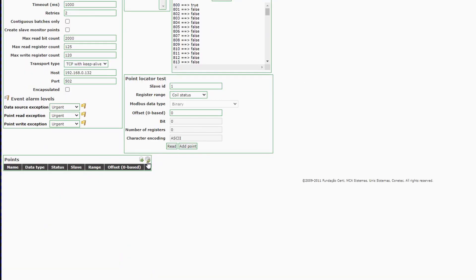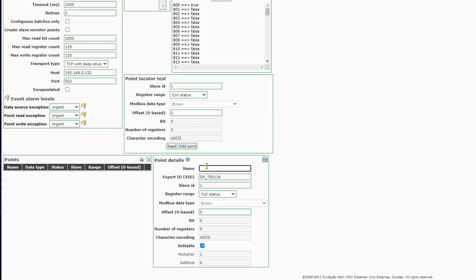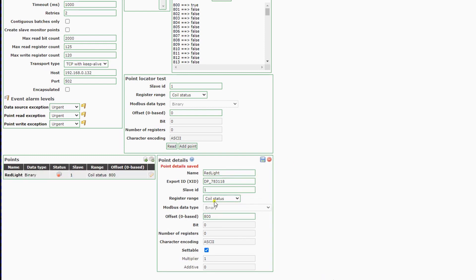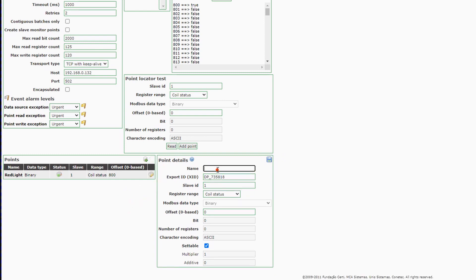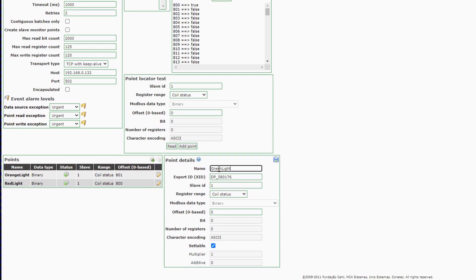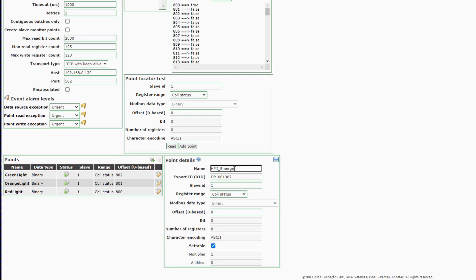Then we will add these data points. The first one we will call 'Red Light'. For the offset we will use 800 because its address is 100.0. We activate the point. We will do this for all three lights — the green light, the orange light, and the red light. The lights are all coils. After we repeat this step for the lights, we'll add the HMI emergency button.